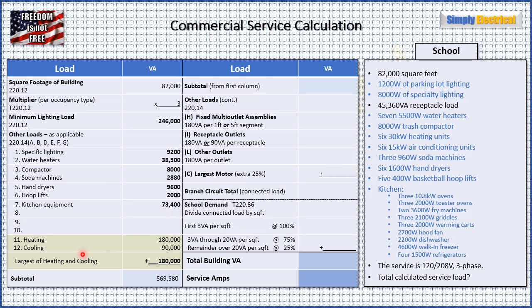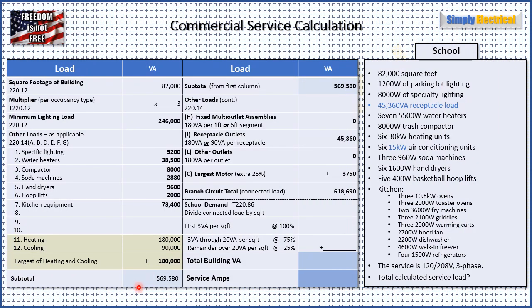Next we get to heating and cooling, which I've pulled into their own section because we need to compare the two. Heating totals 180,000 VA across six heating units; cooling totals 90,000 VA. We take the larger of these two — heating at 180,000 — and add all the bold numbers together. That gives us a subtotal of 569,580 VA, which we carry up to the top of the next column.